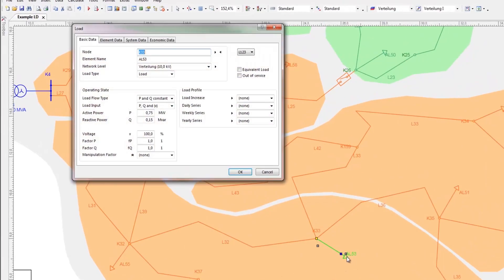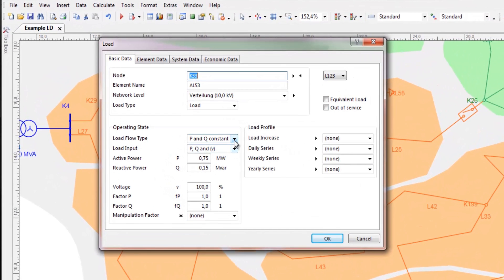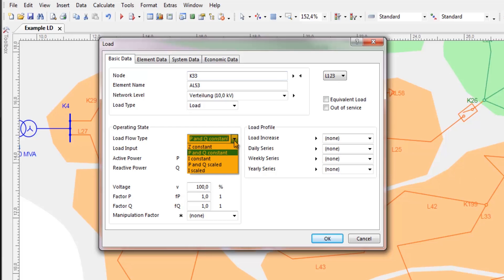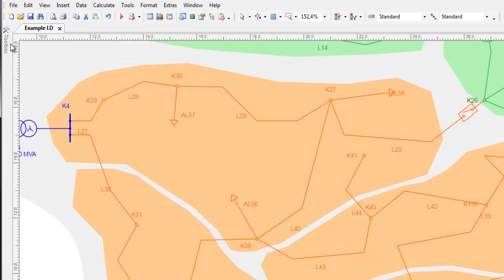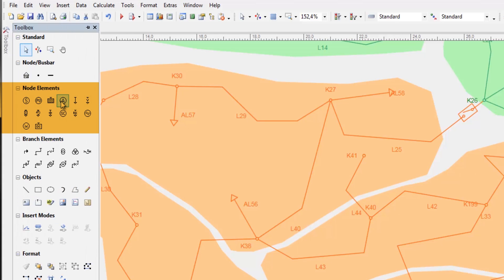The loads in PSS Sincal are just one of seven different load flow types and combinations. How the load is to be entered depends on the networks and the available data — more than 15 different ways are allowed. Motors, including NEMA models, can be modeled more in depth. DC equipment, like solar generation, wind, or batteries, are also modeled separately in PSS Sincal to reflect their specific behavior.